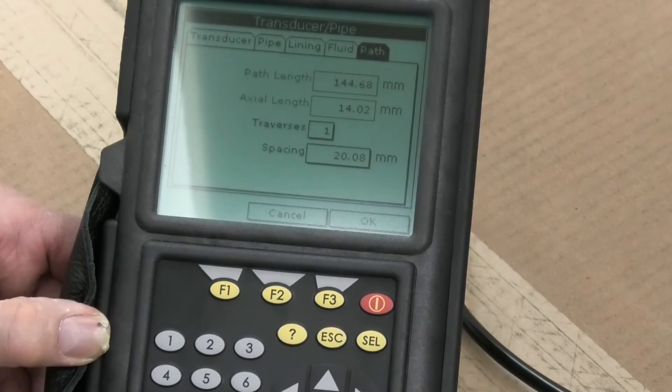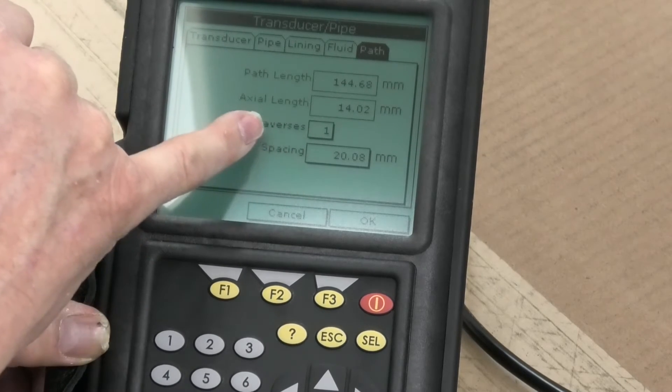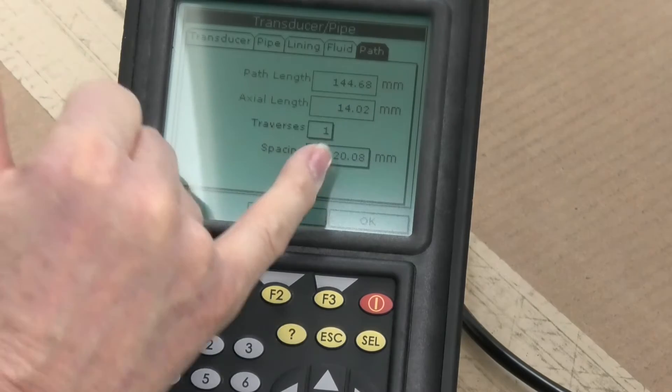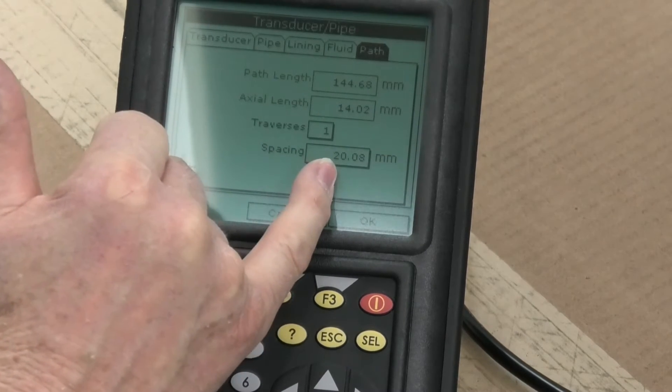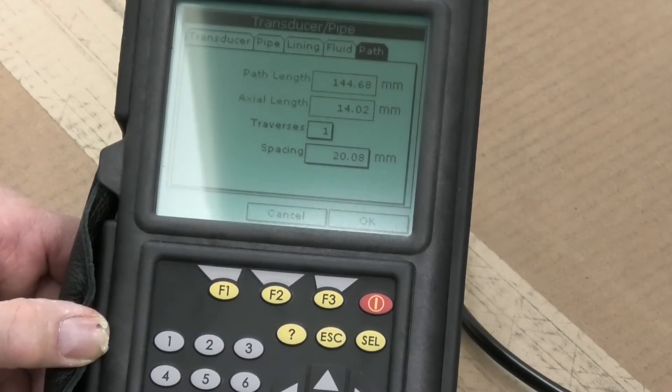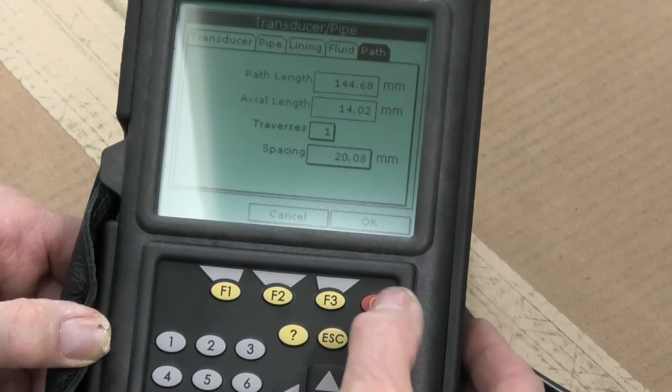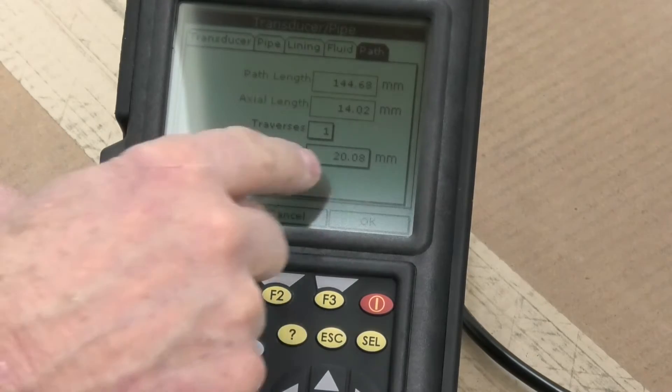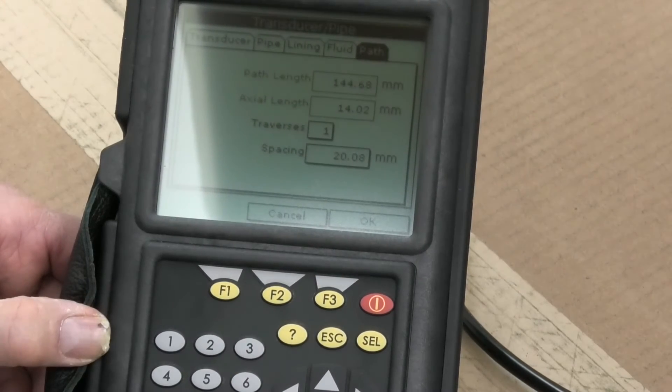Now the other point we've got to do over here, we come over to path. We usually use single traverse with gas measurement. In this case I'm using single traverse. This distance here is important, 20.08mm. That's how far apart the two transducers need to be. Once we push okay, the instrument is set up.